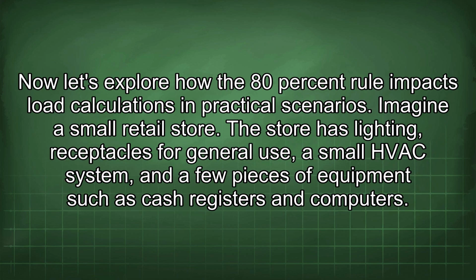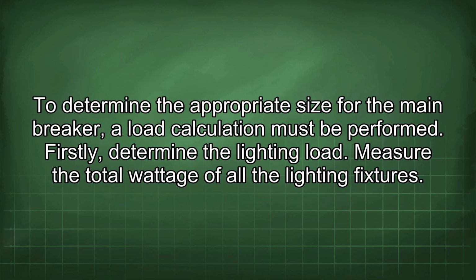Now let's explore how the 80% rule impacts load calculations in practical scenarios. Imagine a small retail store. The store has lighting, receptacles for general use, a small HVAC system, and a few pieces of equipment such as cash registers and computers. To determine the appropriate size for the main breaker, a load calculation must be performed.